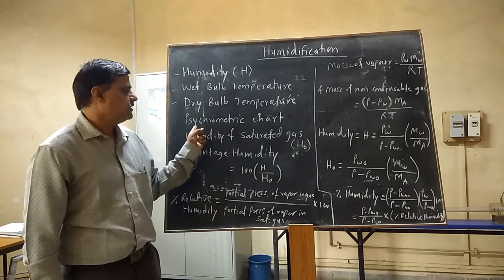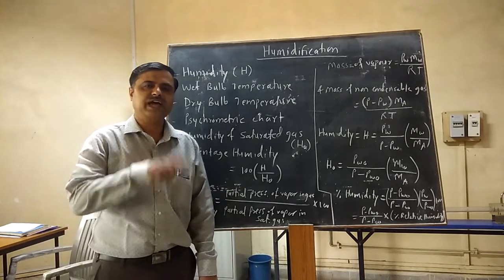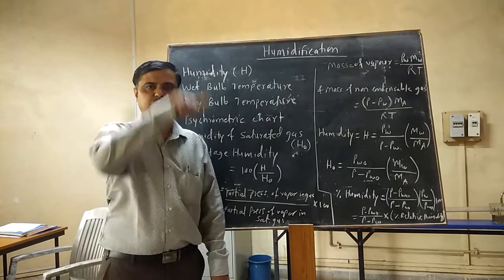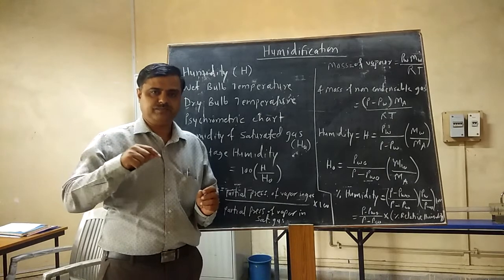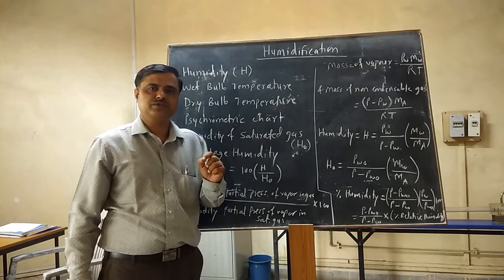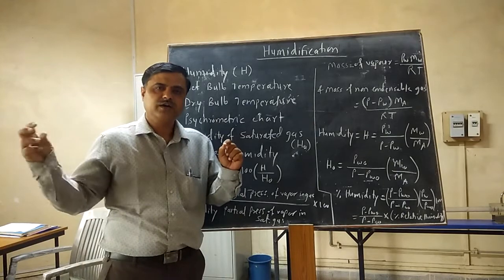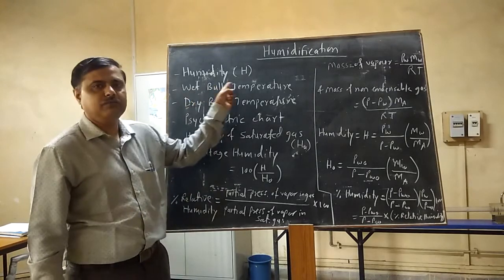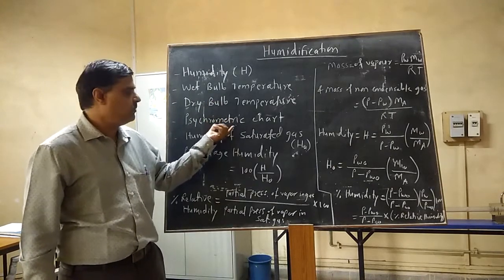By using these two temperatures we can measure the humidity, using the psychrometric chart. In the psychrometric chart, vertical lines are provided for the dry bulb temperature, and different curves are provided depending upon the percentage saturation. You find the intersection point of dry bulb temperature and wet bulb temperature, trace it to the right side, and on the y-axis you get the humidity.